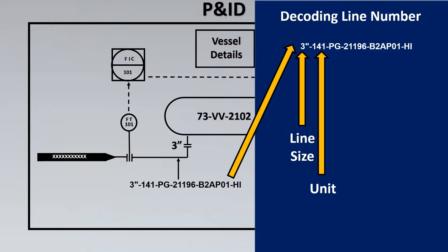The second thing is the unit. Which unit is it belonging to? So plants are usually divided into various units like 141, 143, etc. PG stands for what is the fluid code. So here it's process gas for example. So you understand what type of fluid. If it's hydrogen you might need to have some special precautions, etc. So fluid code helps us to understand what is inside that line.